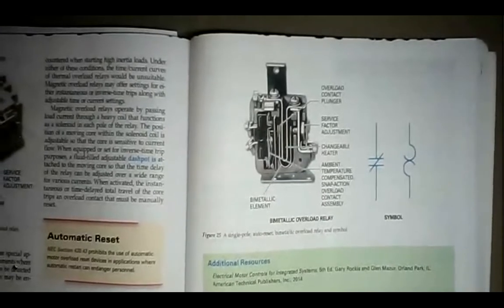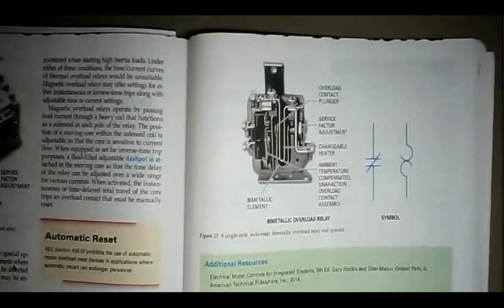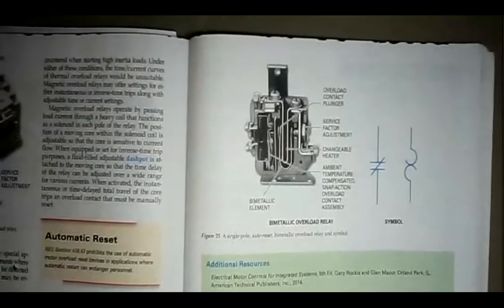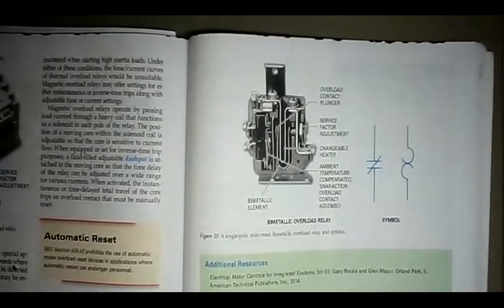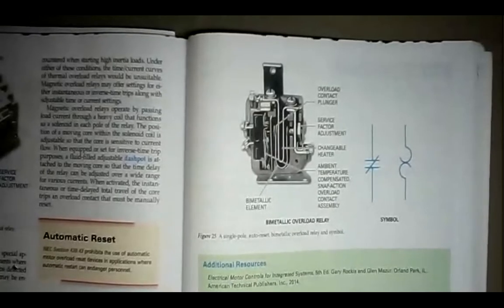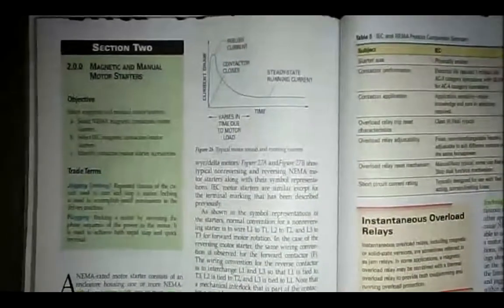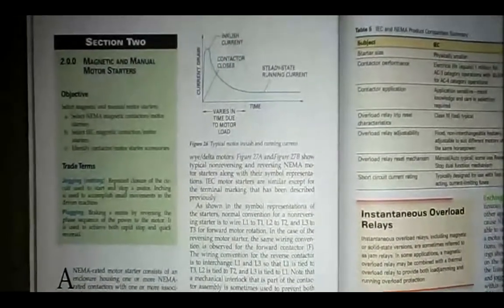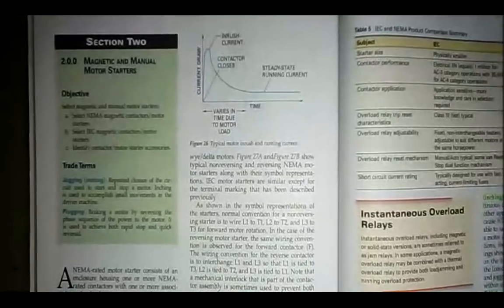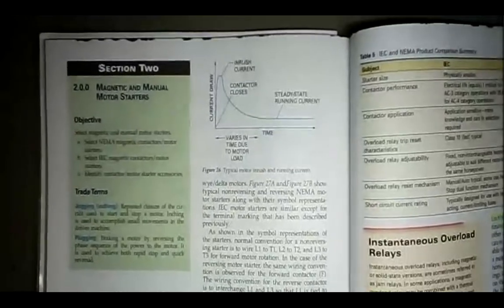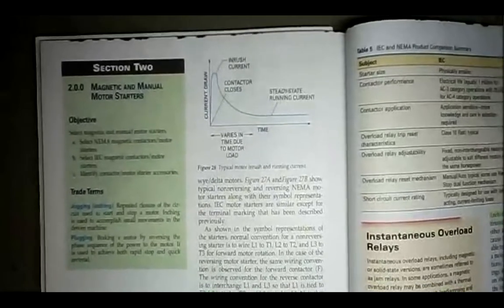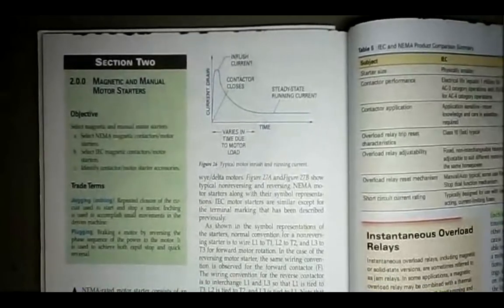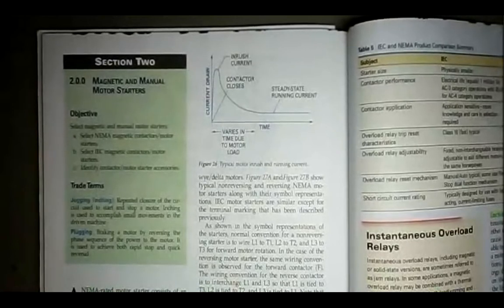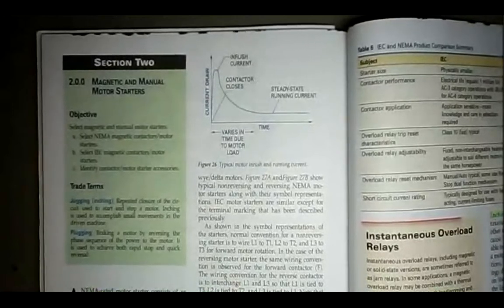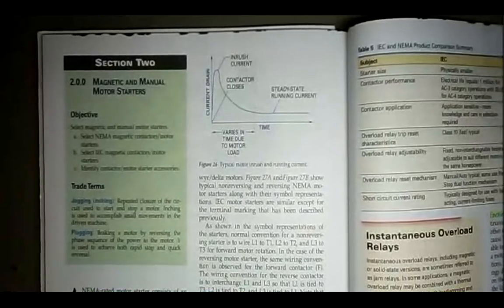You also need short circuit protection because these overloads do not protect a motor from short circuit. You need to have it on either a motor controller, which is like a circuit breaker, or you need to have it protected by fuses. Okay. Here on page 22 at the top of the right-hand side, they're actually talking about starting current. Starting current can be 6 to 8 times the value of the run current.